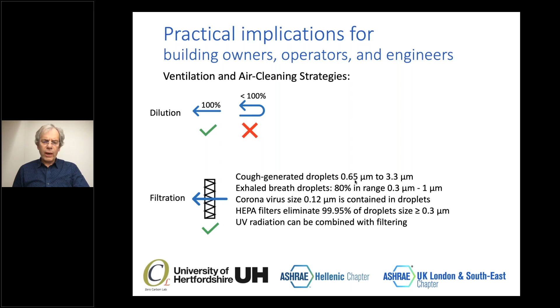When it comes to airflow strategies, there's evidence that unidirectional low velocity flow works in a similar way as a piston in the internal combustion engine, as it cleans everything in the space in which it operates. That is pretty much achieved by single space high efficiency filtration units that achieve directional airflow.